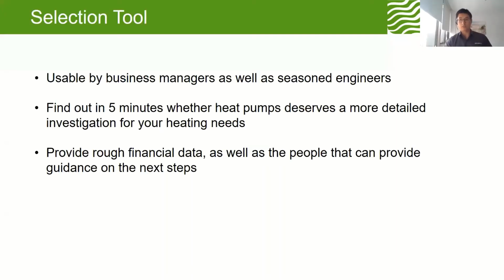So for the next couple of minutes, I'll take you through the use of this selection tool. Our goal, as I said previously, was to incorporate all the factors that we've just described into this tool numerically or into a series of talking points that will come up as you use the tool. One of the biggest challenges with using heat pump technology to replace process heating is the complicated nature of a heat pump's operation. There are often more than 2 thermal streams, all of which are physically separated. And the thinking around heat pump design also differs a lot from traditional boiler design, where the focus has always been to provide peak heating loads. Instead, we're looking at providing average loads and then using thermal storage to accommodate peak demand.